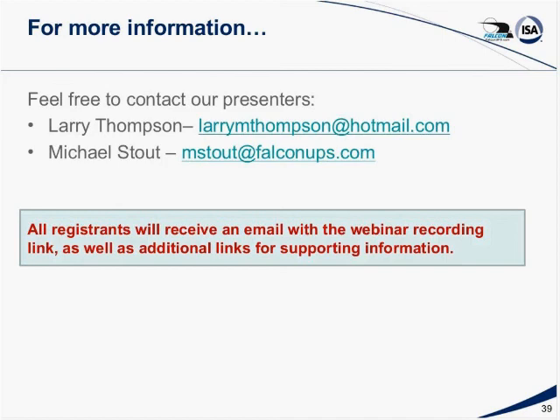All right, now we just had a question that came in, Mike, concerning communication. How do I talk to my SCADA systems? What options do I have to monitor my network? Most UPS companies offer several ways to monitor the UPS. The industry has decided on the first method, which is SNMP, Simple Network Management Protocol. And the UPS industry has a standard MIB, or Management Information Base file. A lot of manufacturers have a second MIB that supports their extensions for the UPS. And those SNMP boards also usually support HTTP, so there's an embedded website inside the UPS. They're all TCP addressable, and I think they use Ethernet communications protocol.